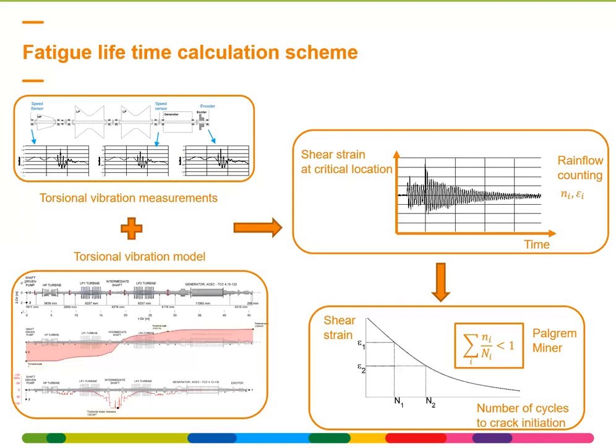So the torsional vibration model shows you the correlation between a torsional vibration amplitude that you measure at a certain position and the stress that the shaft experiences at any other position. So torsional vibration measurement is a model-based monitoring. You're not measuring at the critical location, but at a point where you have high torsional vibration amplitudes, for instance, and you use the model to determine the stresses at a different location on the shaft line. So this is important to highlight. You need the torsional vibration model to assess the criticality. This has to be done for every natural frequency.